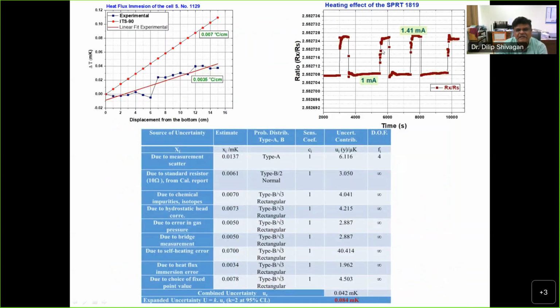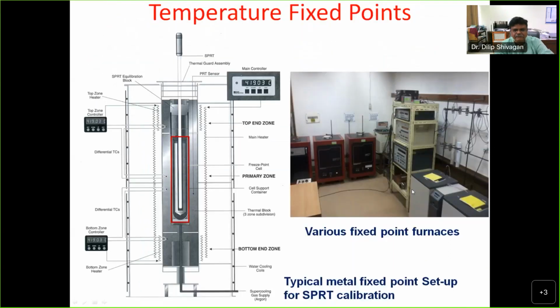And as I said, this thermometer has Joule heating, so you can vary the current and know the heating effect, what is the rise in delta R. Based on that, you can calculate, because all those are very important when you are going to define the uncertainties of the level of say 0.1 or 0.17. Because this heating effect itself is about 1.7, you need to correct it very carefully. So all the corrections need to be applied, and then you evolve the uncertainty.